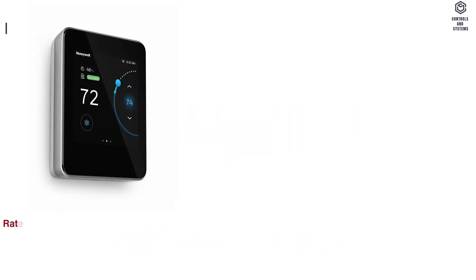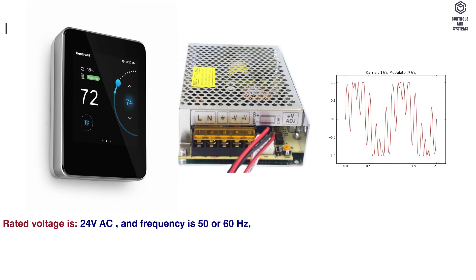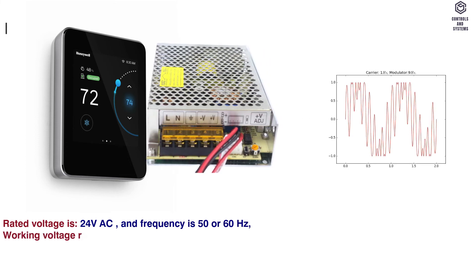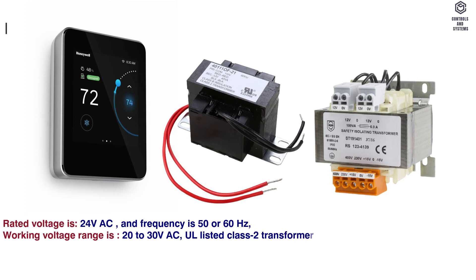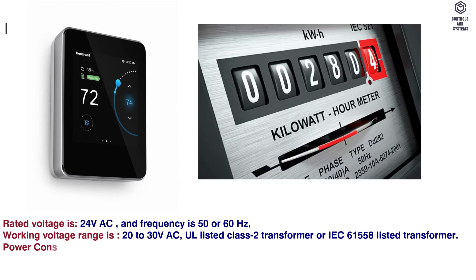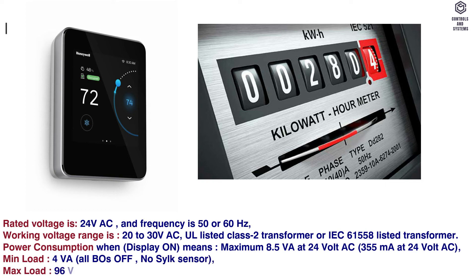Technical specifications — Power supply: Rated voltage is 24V AC at 50 or 60 Hz. Working voltage range is 20 to 30V AC, using a listed Class II transformer or IEC 61558 listed transformer. Power consumption with display on: maximum 8.5 VA at 24V AC, 355 milliamps at 24V AC. Minimum load: 4 VA with all outputs off and no Sylk sensor. Maximum load: 96 VA with all outputs on.